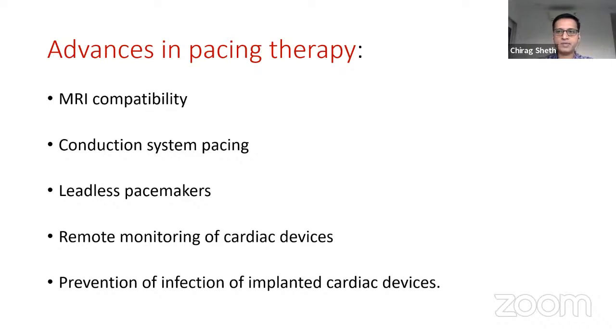First is MRI compatibility. MRI compatibility is now there, at least in the Indian market, for almost a decade. And most devices implanted fresh in the last decade are MRI compatible. We still need to be sure about device specifications. Some devices may be compatible with 1.5 Tesla MRI, but most have now converted to 3 Tesla MRI compatibility.